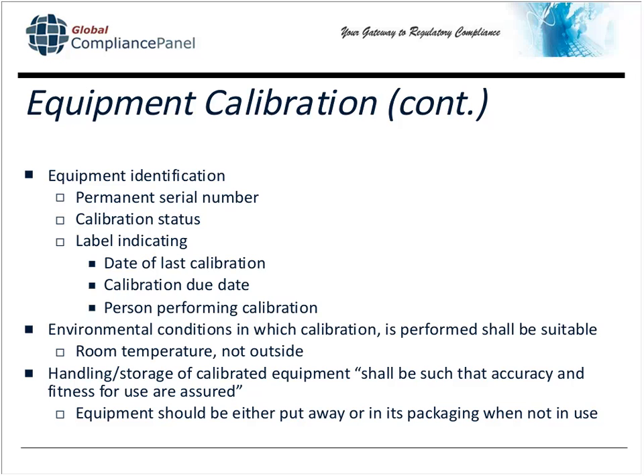You also want to make sure, when it comes to calibration, that the environmental conditions in which the calibration is performed are suitable. You don't want to calibrate it outside, for example. If it's used in a temperature-controlled location, you don't want to calibrate it in perhaps your warehouse that may not be temperature-controlled. And the requirement when it comes to handling and storage of calibration equipment, the regulation requires that it shall be such that accuracy and fitness for use are assured.